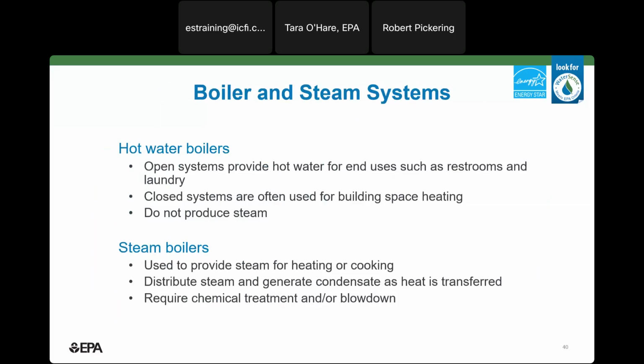So the last mechanical system that we're going to focus on is boiler and steam systems. There are two main types of boilers: hot water boilers and steam boilers. Hot water boilers are either open systems, which produce hot water for domestic consumption or laundry operations, or they're a recirculating closed loop system that's used for space heating. Domestic hot water efficiency is mainly related to the efficiency at the point of use. So installing high efficiency faucets, shower heads, laundry systems, or cooking equipment will save water and energy.